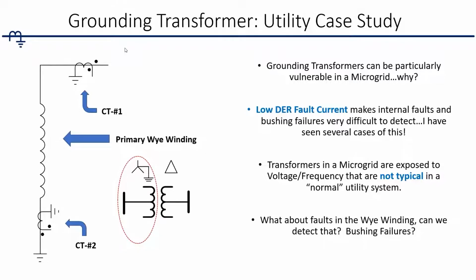Specifically bushing failures too. I've seen two cases in microgrids where the bushings have failed on a transformer and the protection did not operate. It was actively arcing in the field. The technicians reported it and actually had to manually clear the microgrid, and none of the protection operated. So there have been several cases I've seen where this has happened. And most of that can be traced back to either logic and settings, like we said before, or just the fact that it was such a low fault current, it was very difficult for the relaying to detect that.